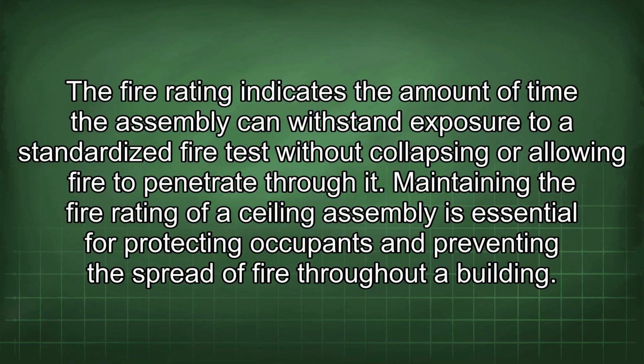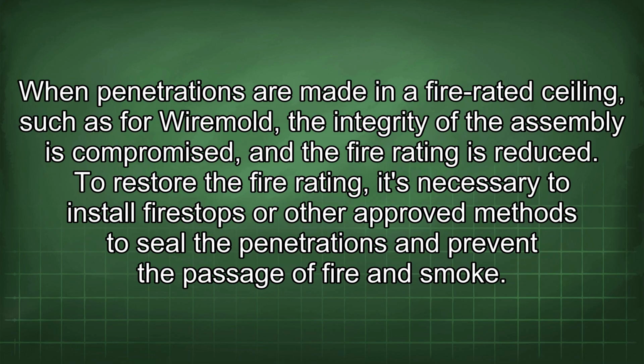Maintaining the fire rating of a ceiling assembly is essential for protecting occupants and preventing the spread of fire throughout the building. When penetrations are made in a fire-rated ceiling, such as for Wiremold, the integrity of the assembly is compromised and the fire rating is reduced. To restore the fire rating, it's necessary to install fire stops or other approved methods to seal the penetrations and prevent the passage of fire and smoke.